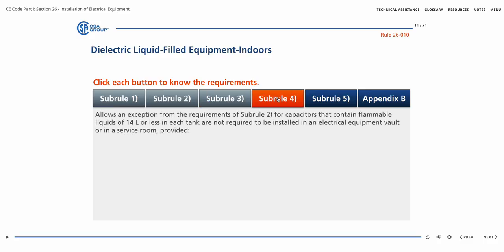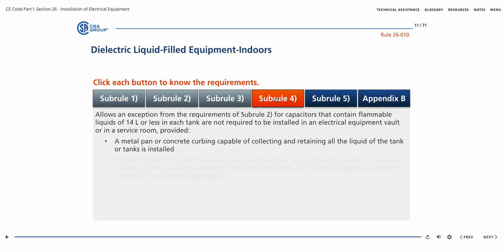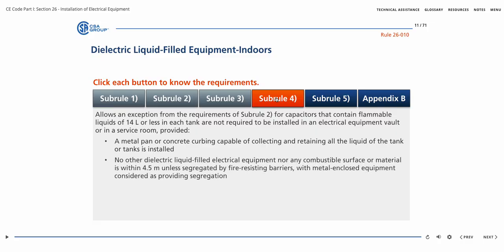Sub-Rule 4 allows an exception to the requirements of Sub-Rule 2 for capacitors that contain flammable liquids of 14 liters or less in each tank. They are not required to be installed in an electrical equipment vault or in a service room, provided a metal pan or concrete curbing capable of collecting and retaining all the liquid of the tank or tanks is installed. No other dielectric liquid-filled electrical equipment or any combustible surface or material is within 4.5 meters unless segregated by fire-resisting barriers, with metal-enclosed equipment considered as providing segregation. Each capacitor tank is provided with overcurrent protection to minimize rupture of the case.